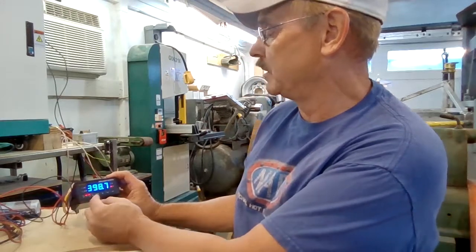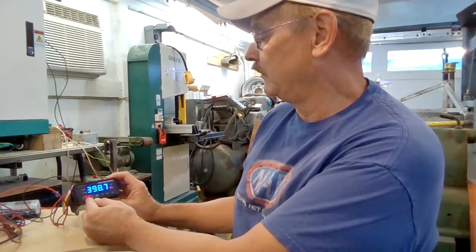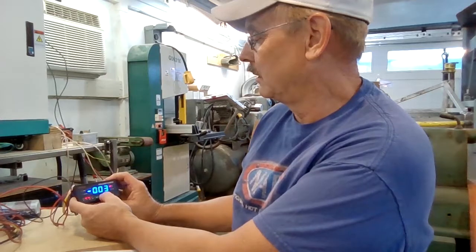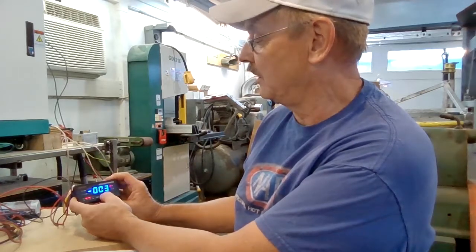Right now it shows J1 contactor is closed, which means the Kilovac contactor is energized. Stepping through the readouts — amp hours, hours, minutes, amps — it's showing that I'm charging at 3 amps at the moment. Some clouds just went over the solar arrays because it was at 10 amps a few moments ago. We're at 398.8 volts according to this, and 396.7 volts according to the inverter up there. Meters all vary a little bit.